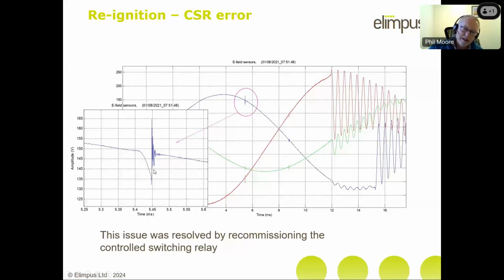And of course, remember what I said about arcs reigniting when the contacts are apart. It's not a very good thing. And so we end up with this signal here. It also produced a very large RF signal as well, so we knew exactly what was happening. When we measured this for about 10 operations, we discovered exactly the same thing every single time the circuit breaker operated. And to cut a long story short, there was an error in the controlled switching relay.